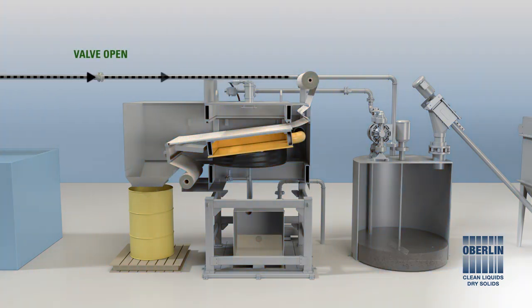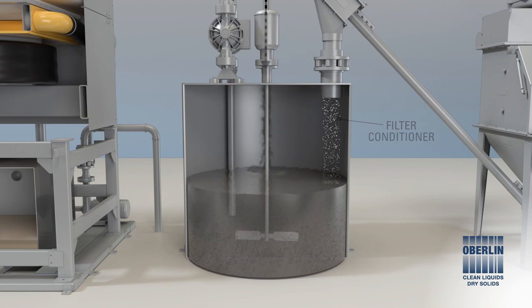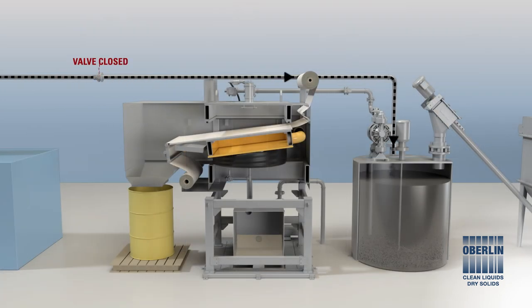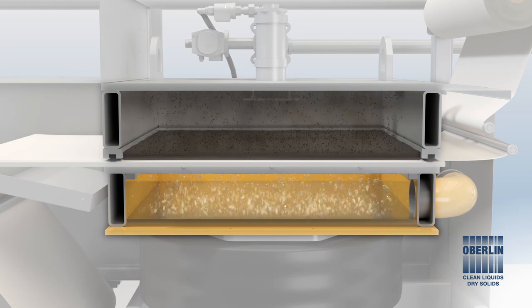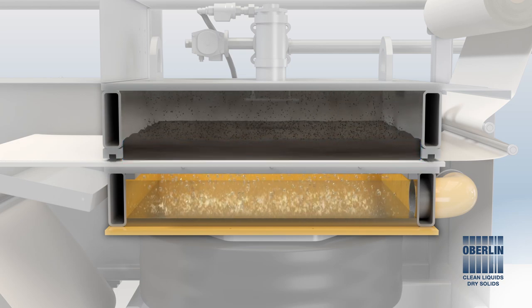Dirty scrubber water is transferred to the treatment tank and conditioner is automatically added per batch. The filtering cycle begins with the filter chambers closing and sealing against a section of filter media. Dirty water is pumped from the treatment tank into the upper chamber, where dirt solids are trapped and clean filtrate drains to the lower chamber. What makes the Oberlin pressure filter so efficient is our Dirt Filters Dirt process — inside the upper chamber, dirty solids collect on the filter media, forming a cake layer that builds as filtration continues, efficiently separating solids below 1 micron.